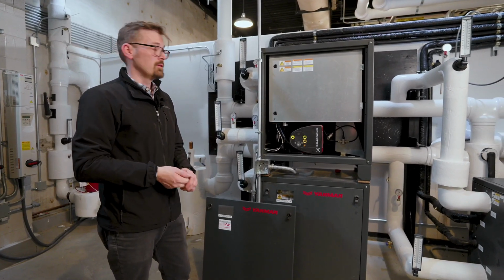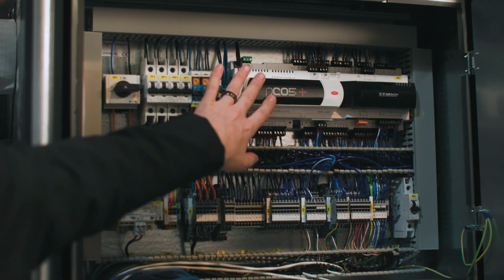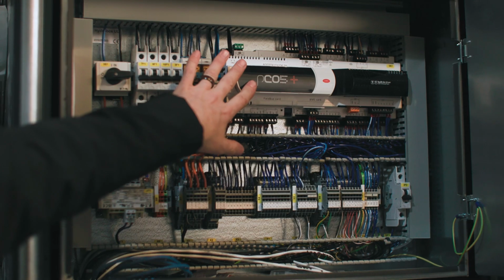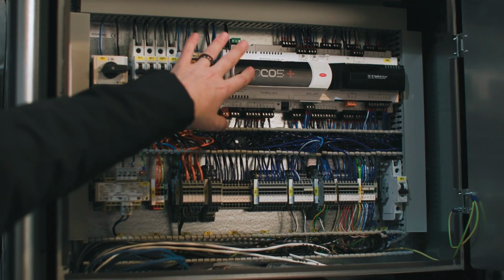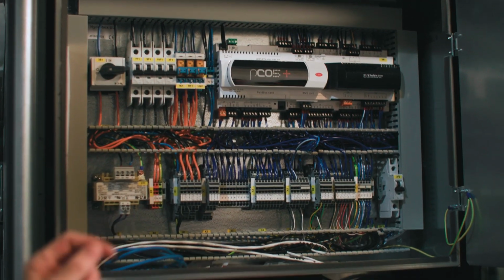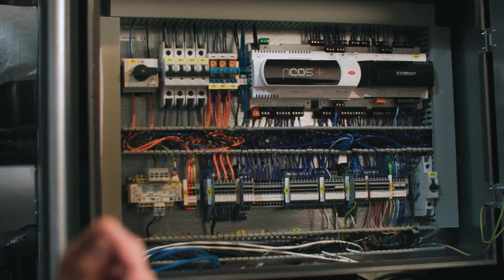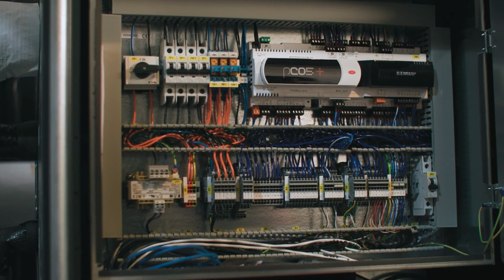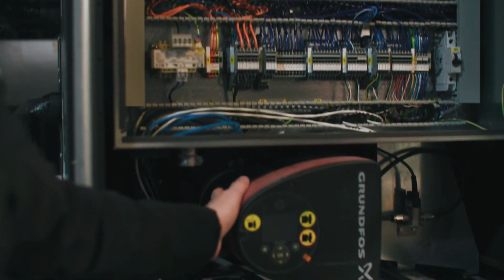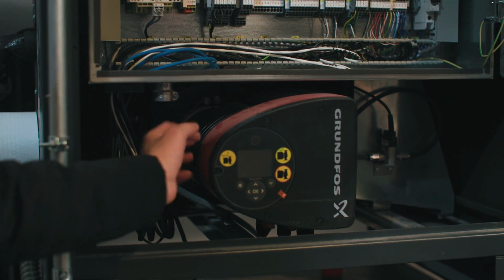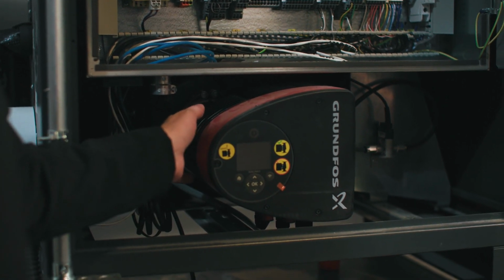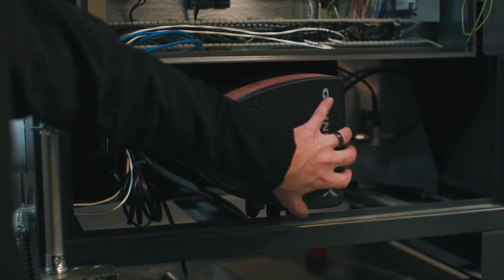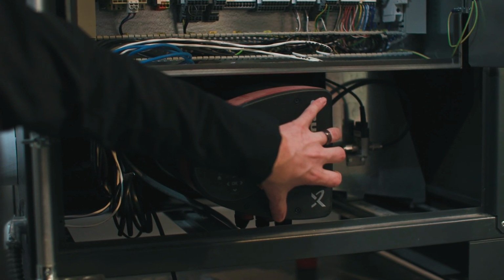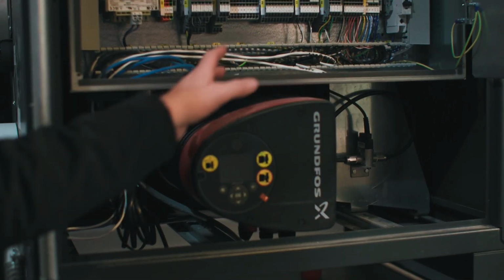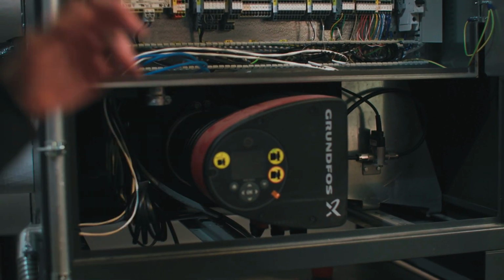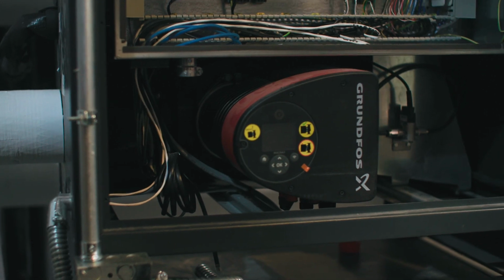These are the main brains of the Hydrobox. This is its main controller, which allows it to communicate between the GHP, the other Hydroboxes, and what other options that you may add into the system overall. This Grundfos pump is what we consider a smart pump. Instead of having a secondary VFD, this is actually the VFD itself, and it'll run along its parameters pre-programmed into it by Yanmar's Hydrobox manufacturing.